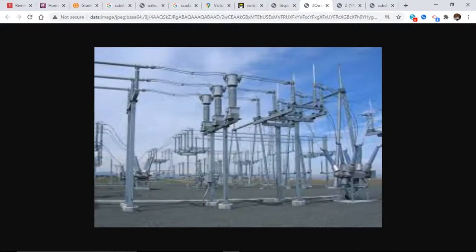So the next component we came to after we had left off before was bus, correct? Yeah. All right, there's plenty, gentlemen, plenty of bus pictures out there. I use this one, it's kind of blurry, I understand, but it had both components in it. You'll notice on this side, this is a round piece of aluminum pipe that's connected electrically. That's what I meant by tubular bus. Now, what's this piece of wire? It is doubled up going to this switch. What type of bus is this? Strain. There you go. It's got both buses in the same picture.